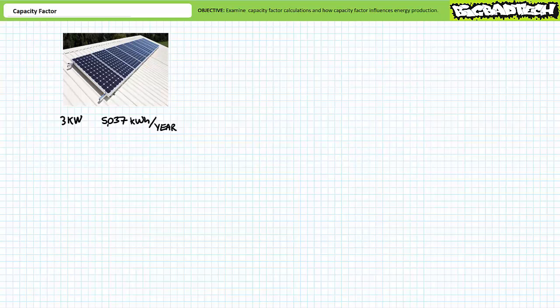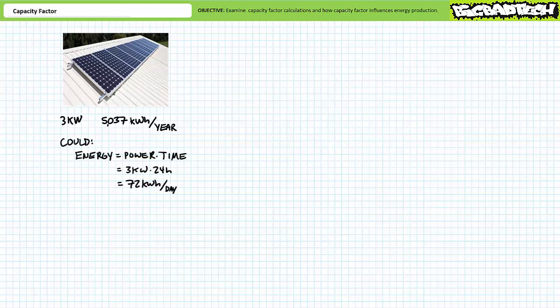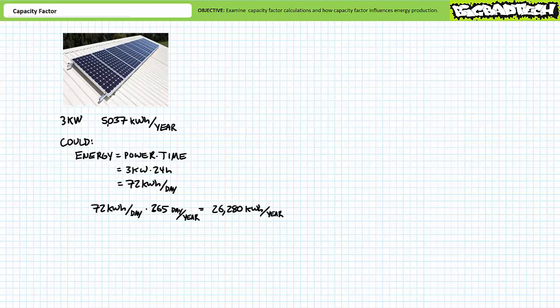Speaking of photovoltaic arrays, consider a small 3 kilowatt residential scale PV system installed on a house in a relatively sunny area of the country known to produce 5,037 kilowatt hours of energy annually. What's the capacity factor of this PV array? Obviously, a solar resource will have a capacity factor of less than 50% because the sun only shines for roughly half the day and during those times it is above the horizon will shine with varying intensity and experience varying cloud cover. Theoretically, this plant could operate 24 hours a day. 3 kilowatts times 24 hours yields 72 kilowatt hours of energy each day. If it did this for 365 days or a whole year, it could theoretically produce 26,280 kilowatt hours of energy each year.